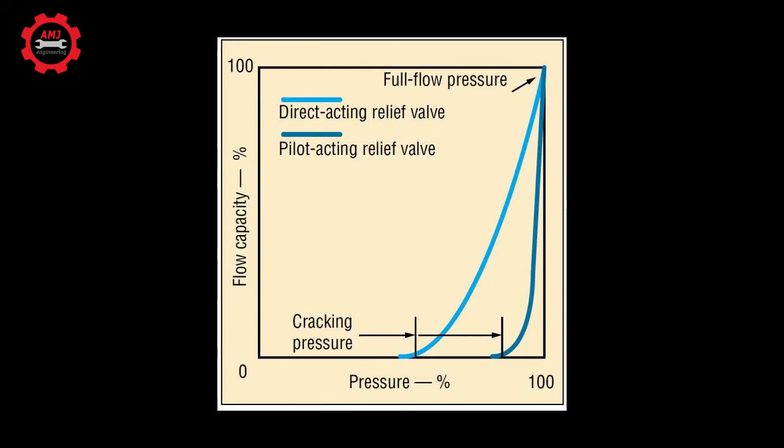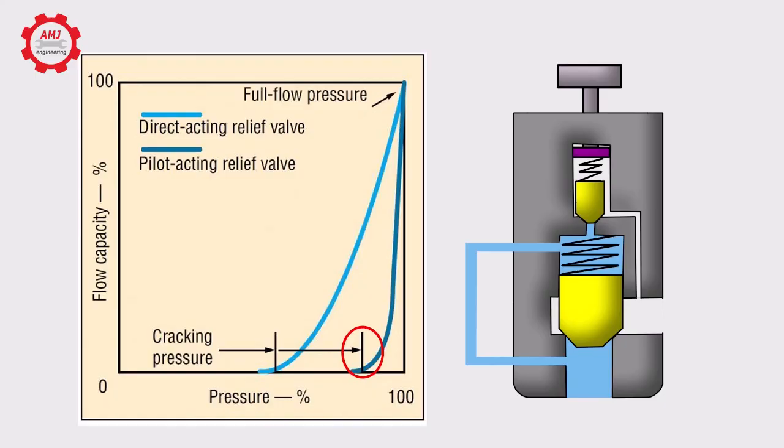This figure shows a comparison of action of relief valves at cracking and full flow pressure. Because pilot operated relief valves do not start opening until the system reaches 90% of full pressure, less fluid is released.